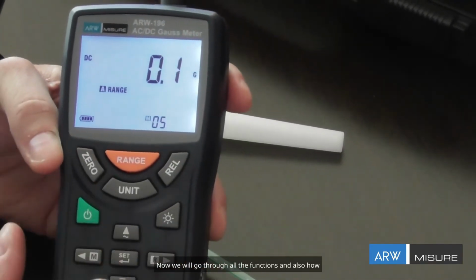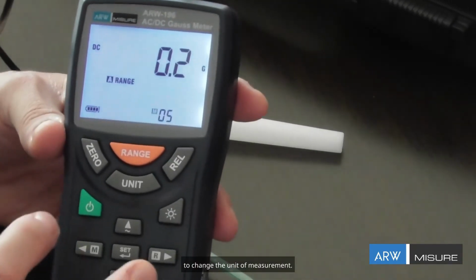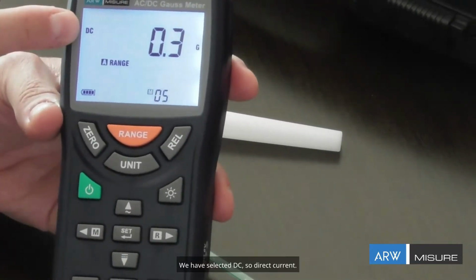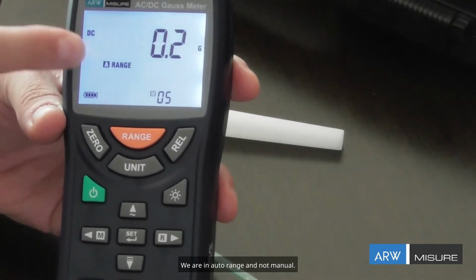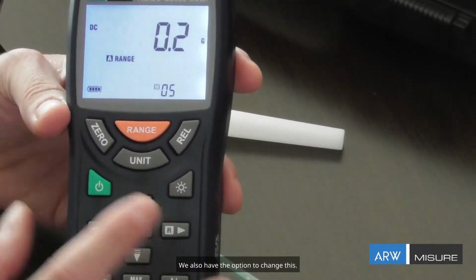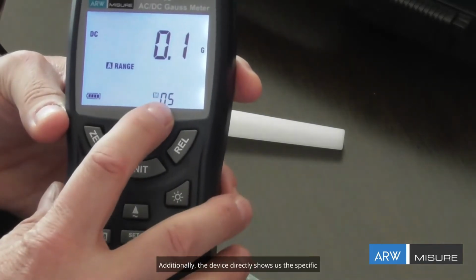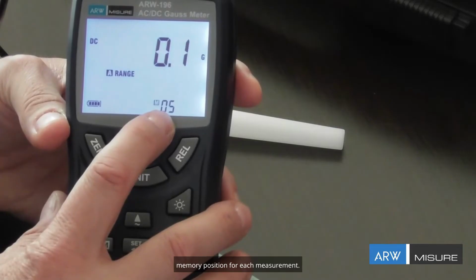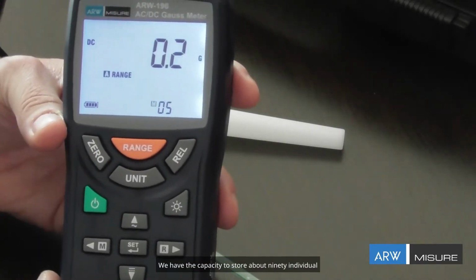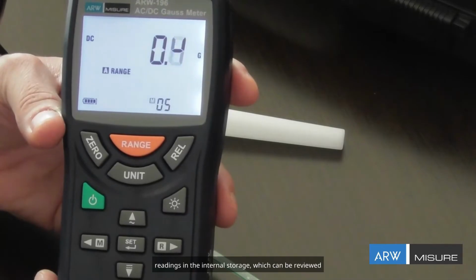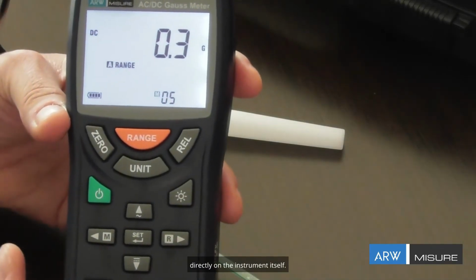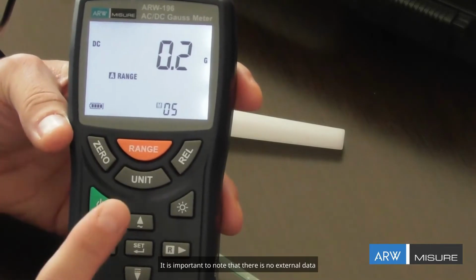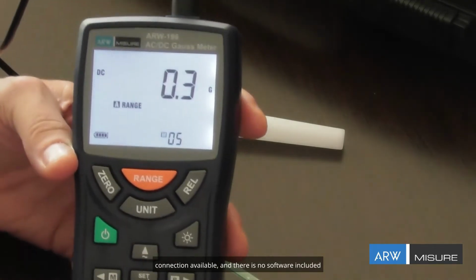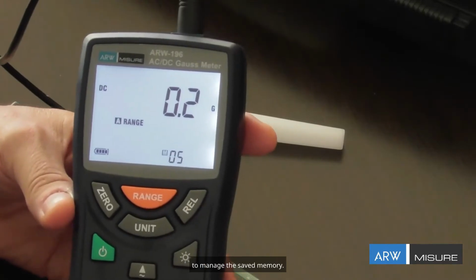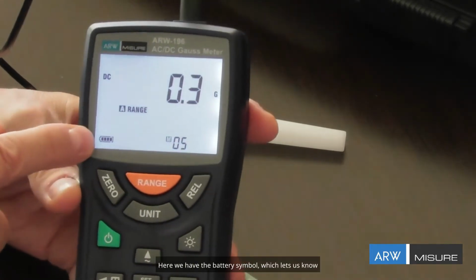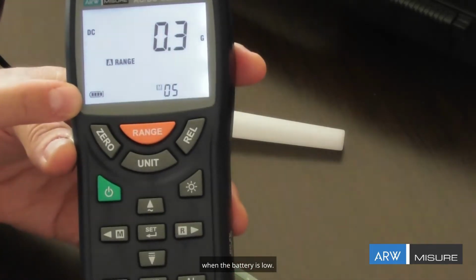Now we will go through all the functions and also how to change the unit of measurement. We have selected DC, so direct current. We are in auto range and not manual. We also have the option to change this. Additionally, the device directly shows us the specific memory position for each measurement. We have the capacity to store about 90 individual readings in the internal storage, which can be reviewed directly on the instrument itself. It is important to note that there is no external data connection available, and there is no software included to manage the saved memory. Here we have the battery symbol, which lets us know when the battery is low.